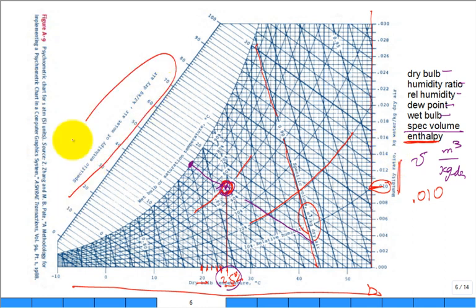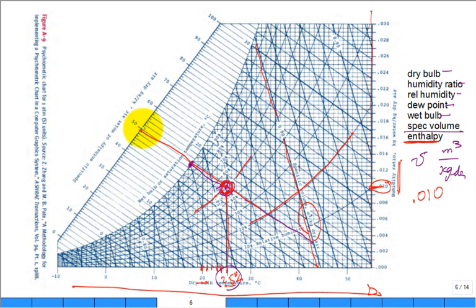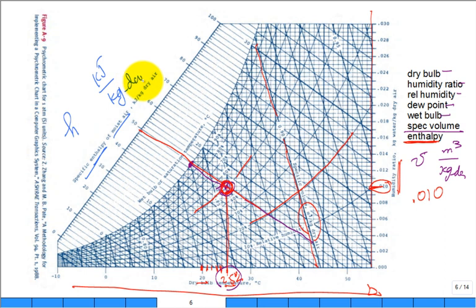The last property is mixture enthalpy. You see it way over here; it's easier to read from that side. If I'm at 25°C and 50% relative humidity and project along the line, it looks like around 49–50 kilojoules of energy per kilogram of dry air. This is the specific enthalpy of the moist air — lowercase h — which includes the energy content of the vapor, but it's in kilojoules per kilogram of dry air.